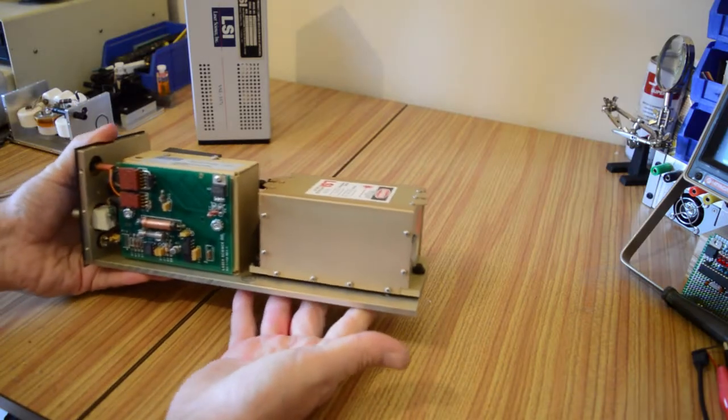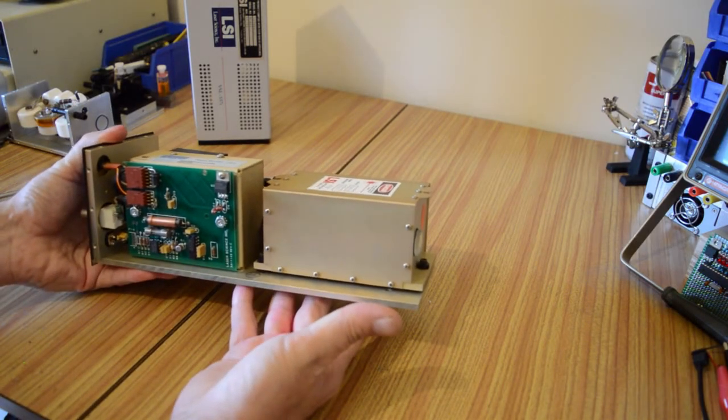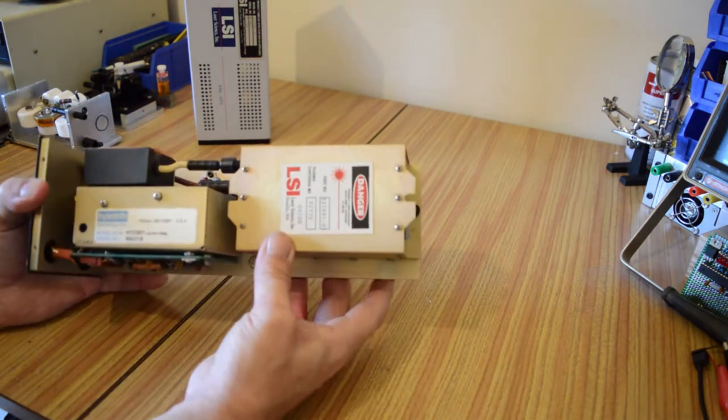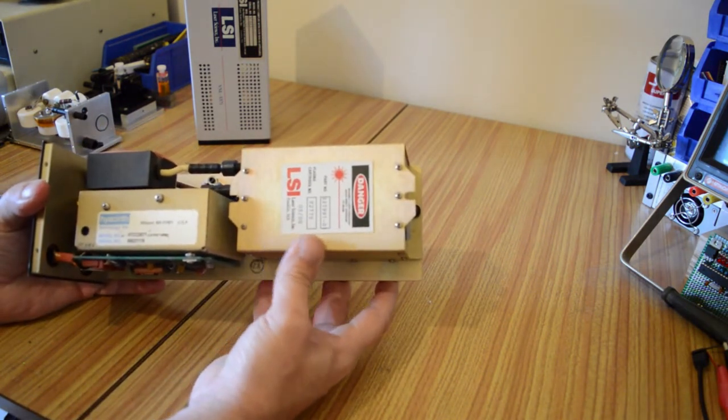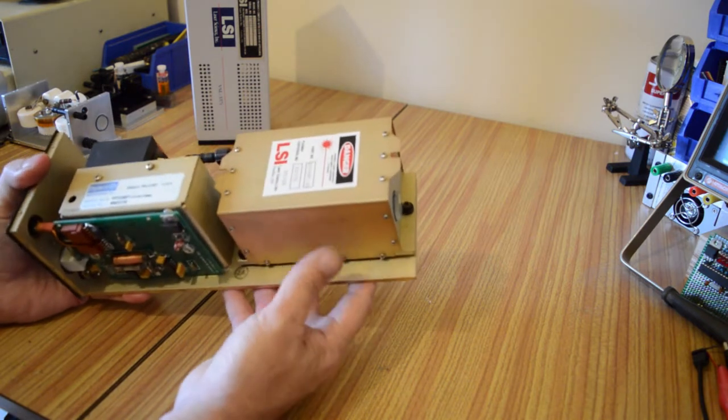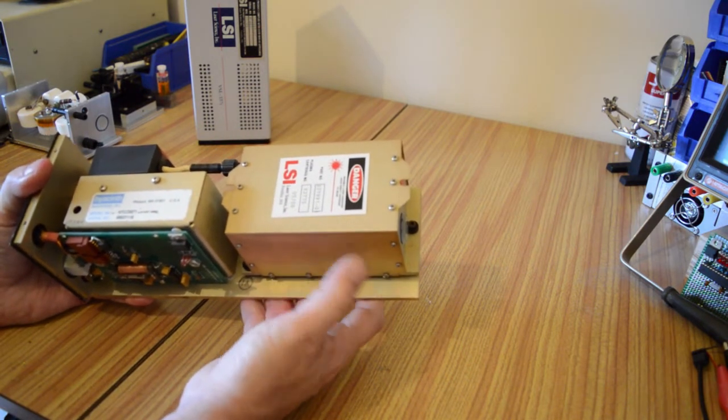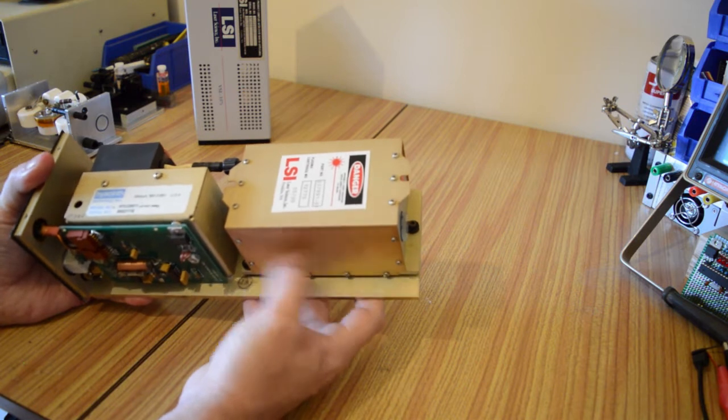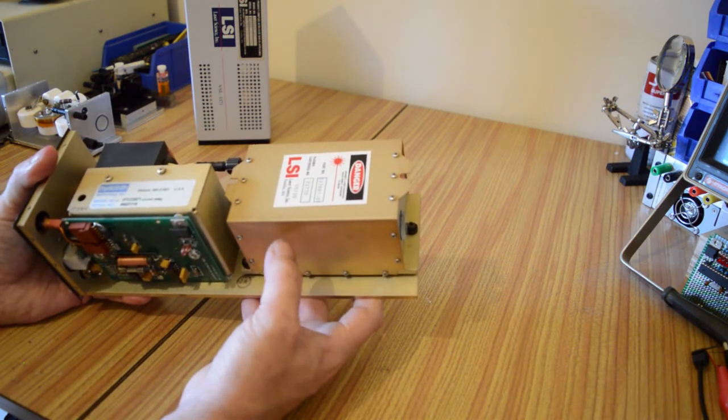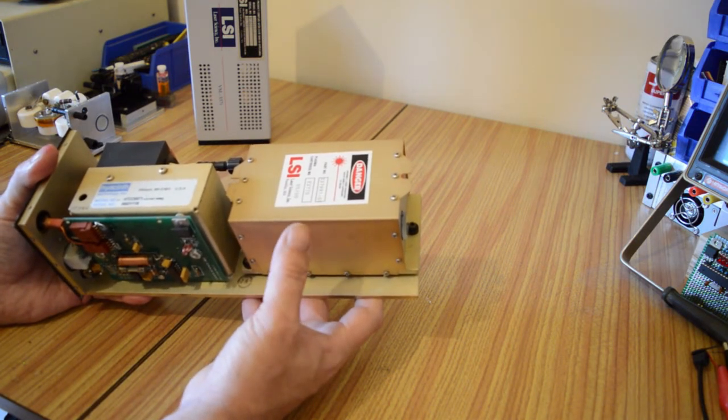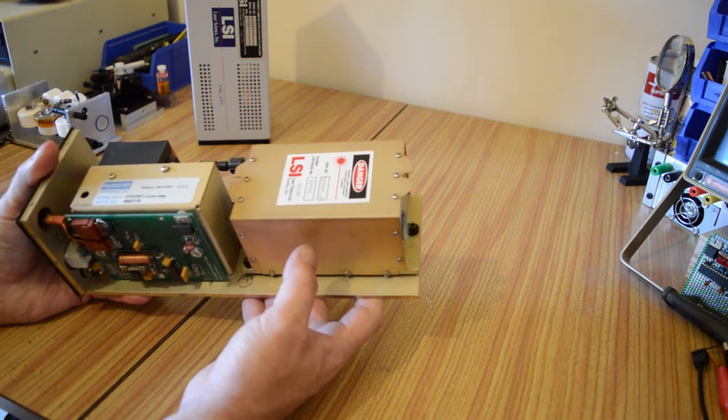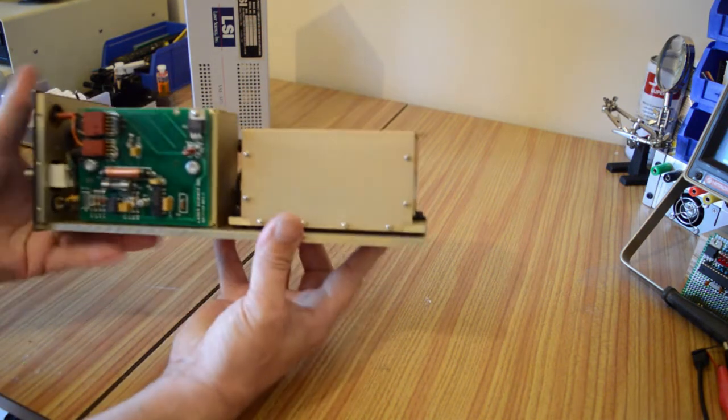So this is the inside of the laser. As I've said, it's not very exciting. We've got the main plasma cartridge here which contains the laser tube itself, the capacitors and the spark gap, and we'll take a look later on at what this looks like on the inside. We can't really undo all the screws on this because it's actually potted inside, full of silicone, but there's one that I have that I've stripped down some time ago that we can take a look at.